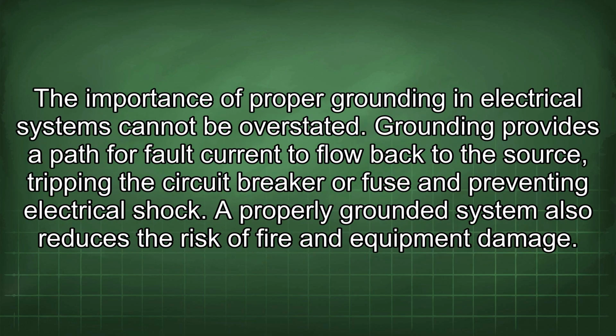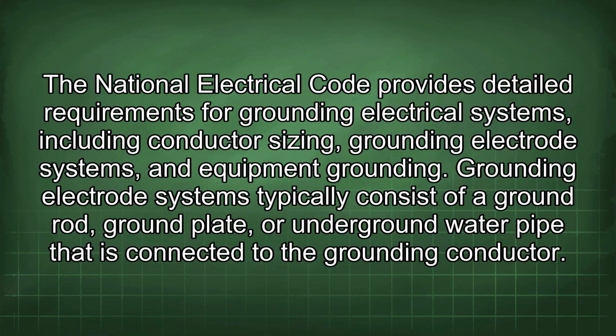The importance of proper grounding in electrical systems cannot be overstated. Grounding provides a path for fault current to flow back to the source, tripping the circuit breaker or fuse and preventing electrical shock. A properly grounded system also reduces the risk of fire and equipment damage. The National Electrical Code provides detailed requirements for grounding electrical systems, including conductor sizing, grounding electrode systems, and equipment grounding.